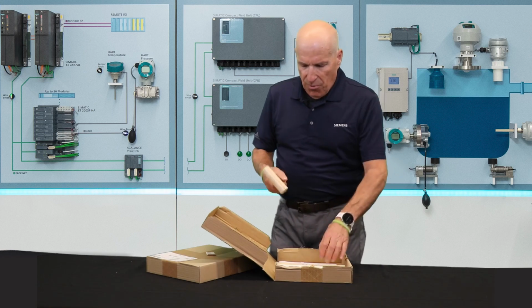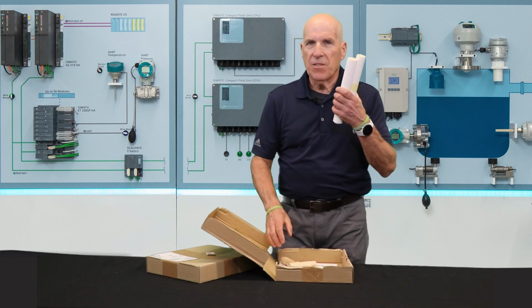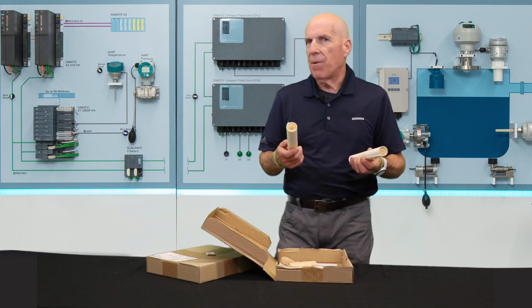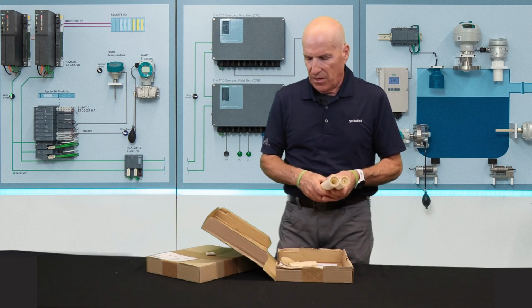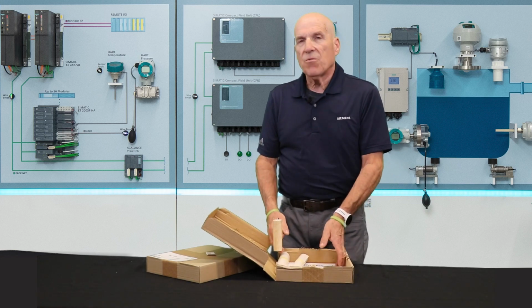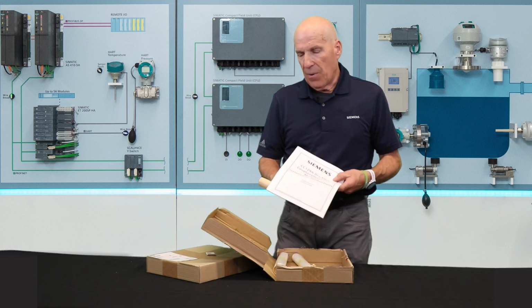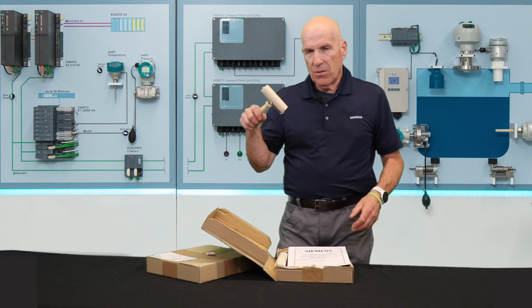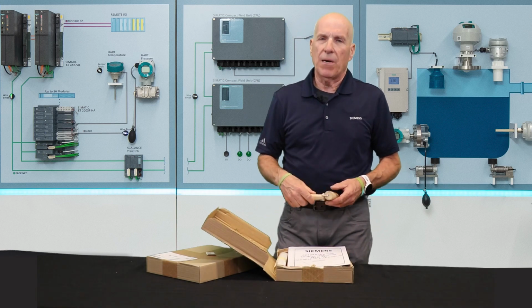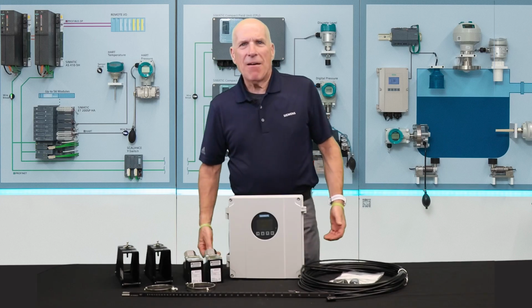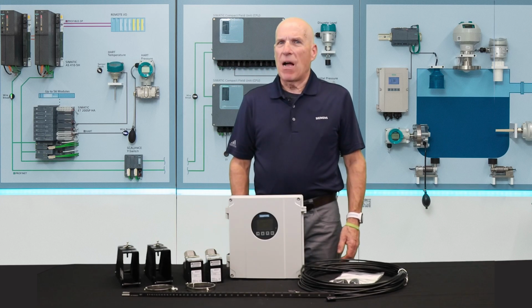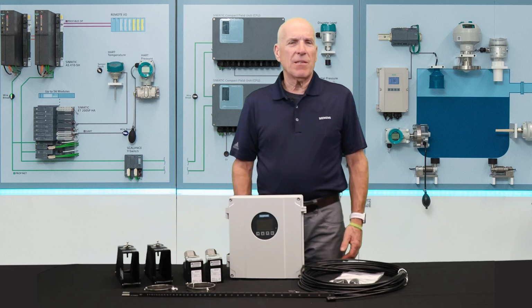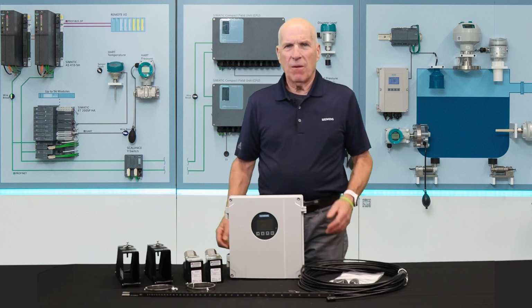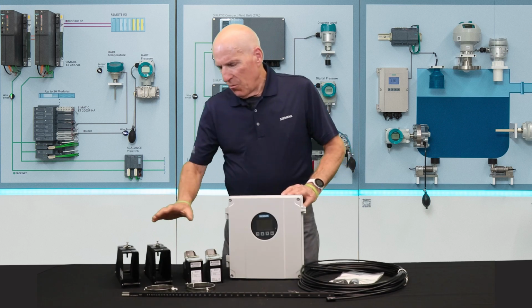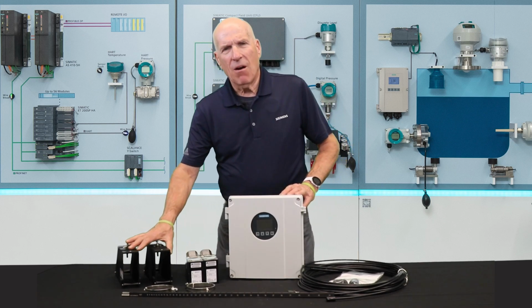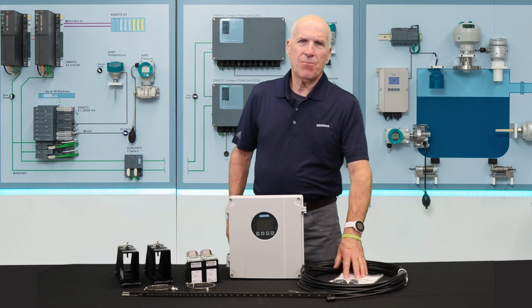The kit is comprised of sufficient damping material to apply to the pipe based upon the size sensors that you received, along with the instructions for installing it on your pipe, and a roller to ensure that it's well bonded to your pipe. So there you have it. While there seems to be a lot of variety, fundamentally each order contains the same 4 components: a transmitter, flow sensors, mounting hardware, and cables.